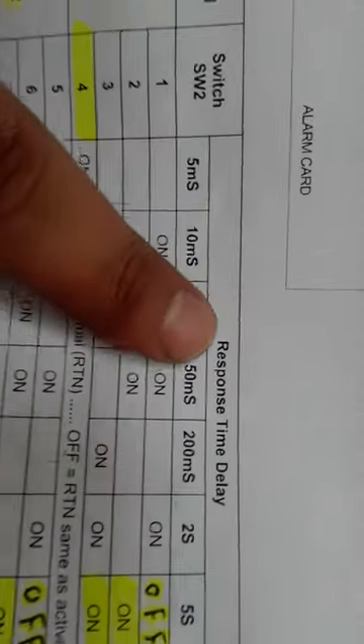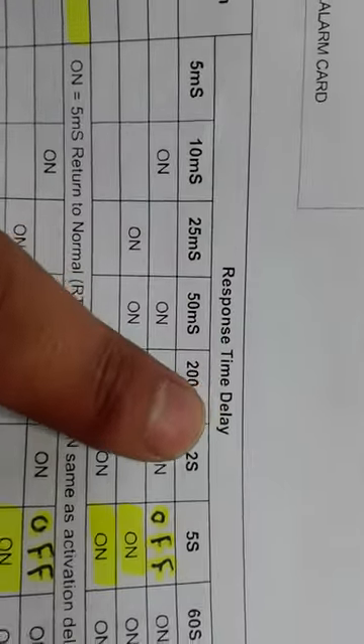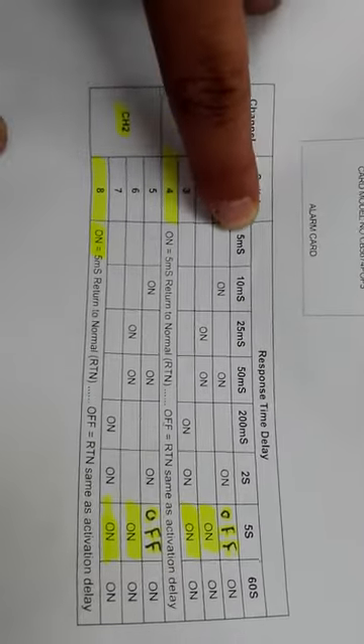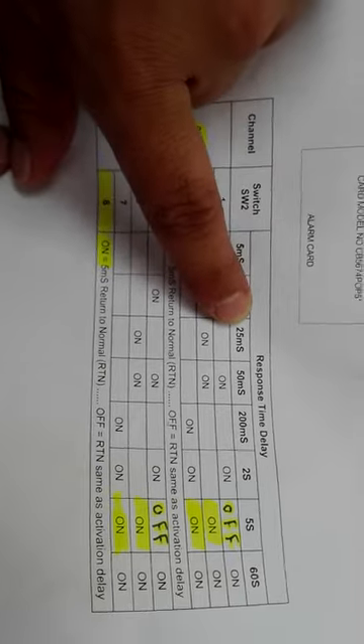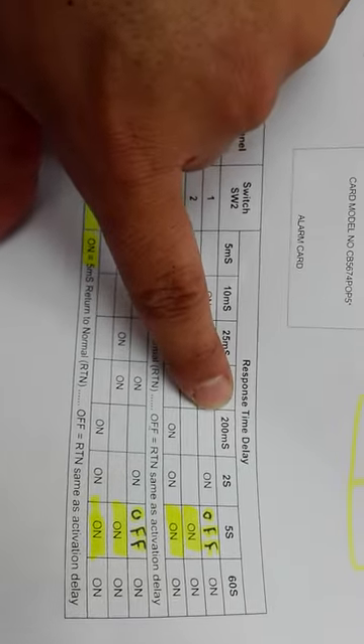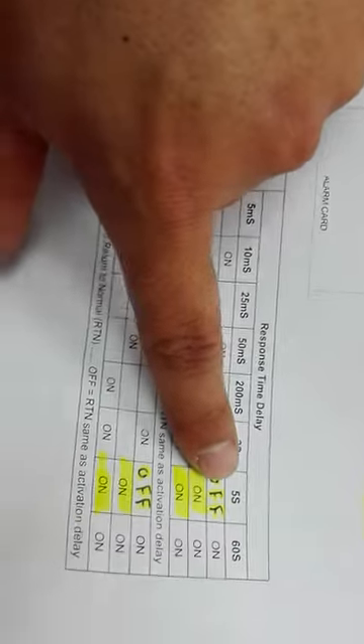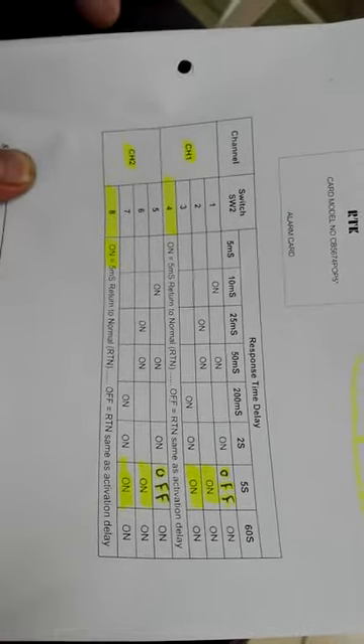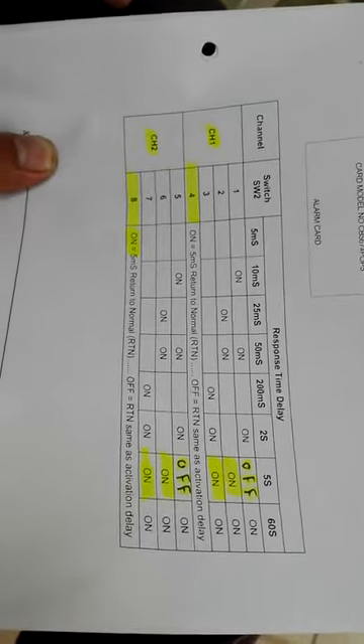Okay, now response time delay: how much time delay after which a channel should respond. It has different types of delays: 5 milliseconds, 10 milliseconds, 25, 50 milliseconds, 200 milliseconds, 2 seconds, 5 seconds and 60 seconds. Accordingly we will make the switch selection.